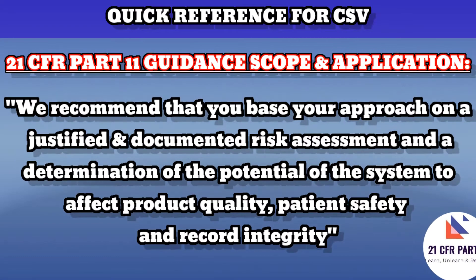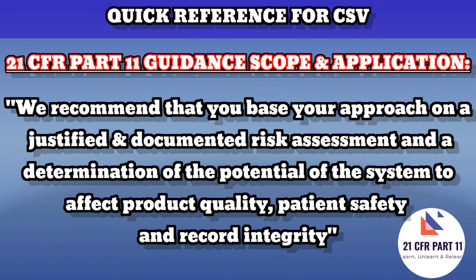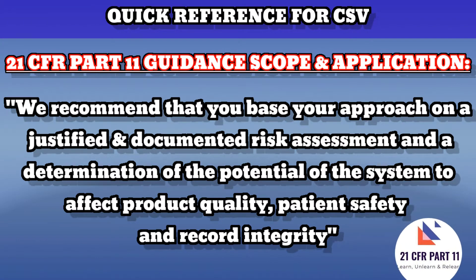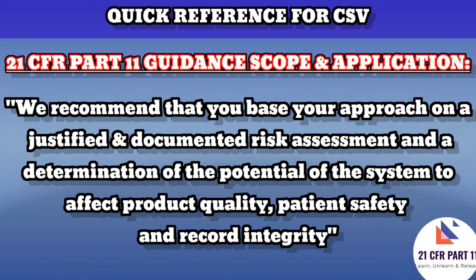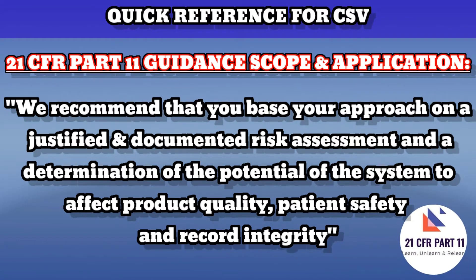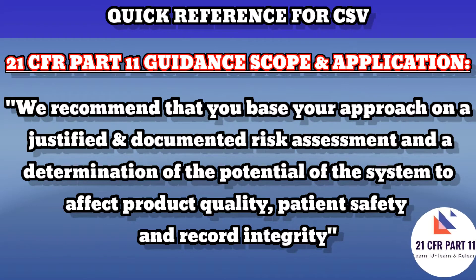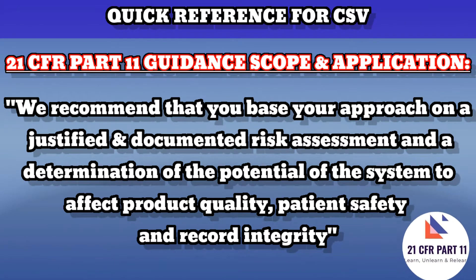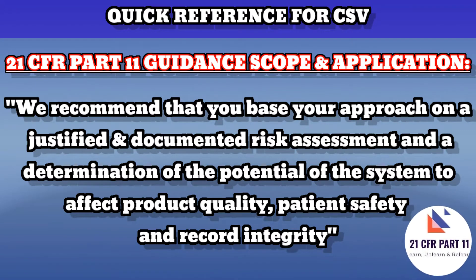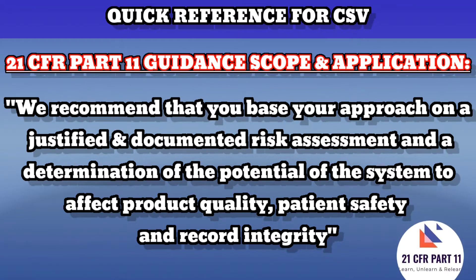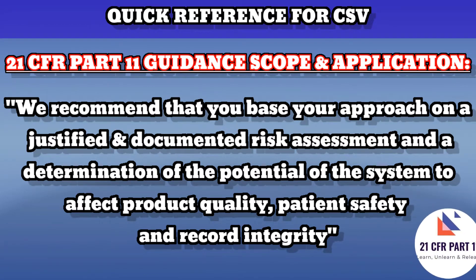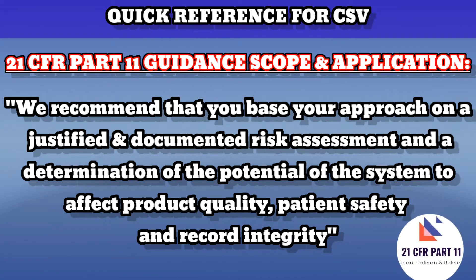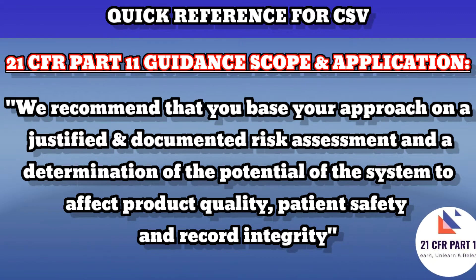The 21CFR Part 11 guidance scope and application says to all companies that we recommend you base your approach on a justified and documented risk assessment and a determination of the potential of the system to affect product quality, patient safety, and record integrity.